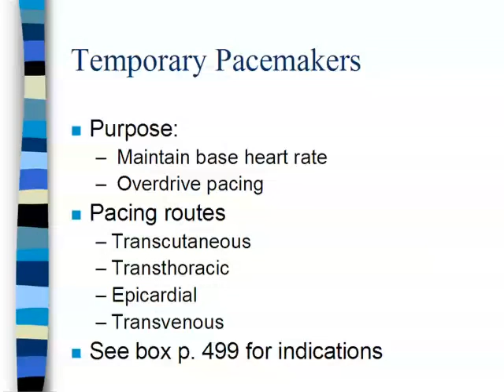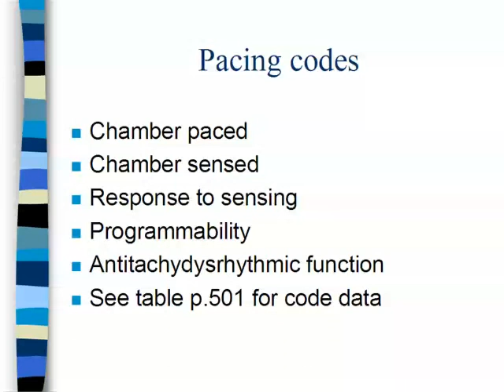Pacing codes identify the chamber paced, the chamber that's sensed. Those codes would be either 0 meaning none, A the atrium, V the ventricle, D whether it's both or dual, T whether it's triggered, this has to do with your response to sensing, or I whether it's inhibited. Then programmability: is it single programmability, your rate, your output, your sensitivity? Or is it M, which means multiple programmability. C means communicating and R means rate responsive. Anti-tachydysrhythmic function means that it provides pacing and shock. So this would be somebody who had an implantable cardioverter defibrillator pacemaker. And there is a table on page 501 that lists all that lovely code data.